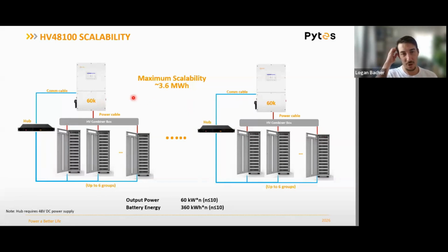Now, if you need a system larger than that, you can have infinite inverters theoretically, as long as they're not connected in parallel on their backup side. What I mean by that is the inverters can be paralleled on the grid side to any quantity you need. But if we're doing backup power, we've got critical loads. That's where that 10 inverter max comes into play.